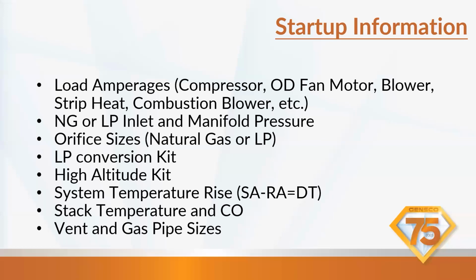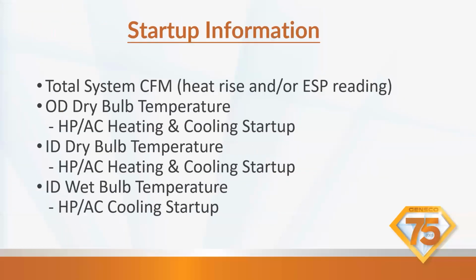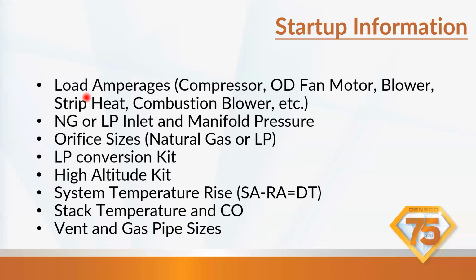Startup information. We're going to want to know your load amperages, what the RLA should be, and then what's your actual amperage on your compressor, your outdoor fan motor, your blower motor, your strip heat, your combustion. All that tells you is you're functioning within the equipment parameters. So if we're not within equipment parameters, why? Why are we not within the parameters? You might have to dig in a little bit deeper to find out what else is going on to prevent a failure in a month.